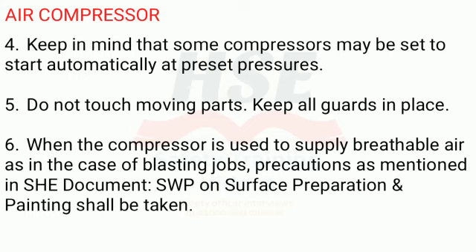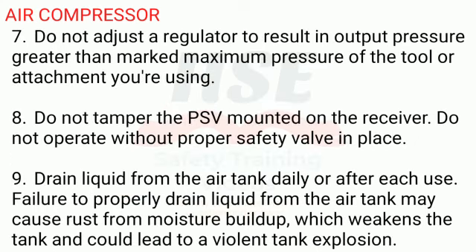6. When the compressor is used to supply breathable air, as in the case of blasting jobs, precautions as mentioned in SHE Document: SWP on Surface Preparation & Painting shall be taken. 7. Do not adjust a regulator to result in output pressure greater than the marked maximum pressure of the tool or attachment you are using. 8. Do not tamper the PSV mounted on the receiver. Do not operate without proper safety valve in place.